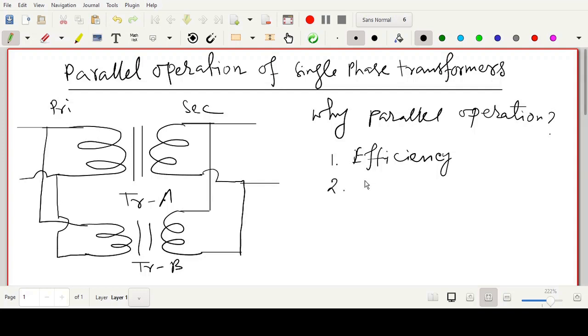Number two is reliability. In case of a single transformer, if the transformer fails, your entire system will be out of power. Now if there are two transformers, and one transformer fails, you can still give power to the system, at a reduced load. In case of a single transformer, you have to shut down the whole thing. So reliability increases. Number three, flexibility.